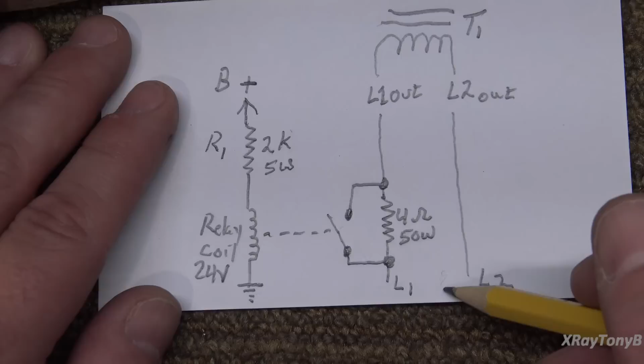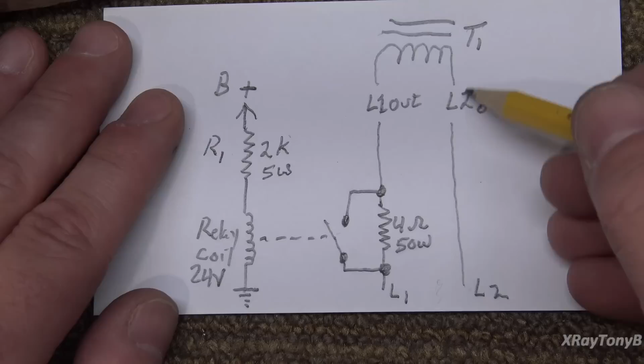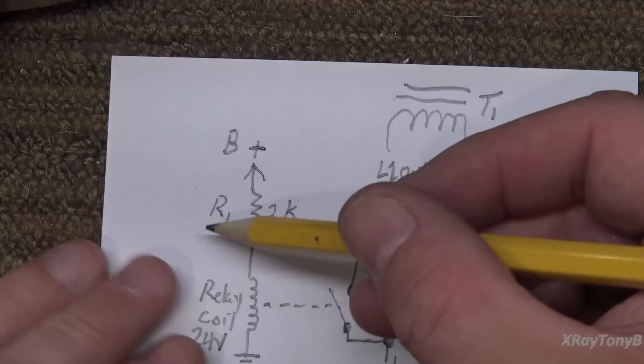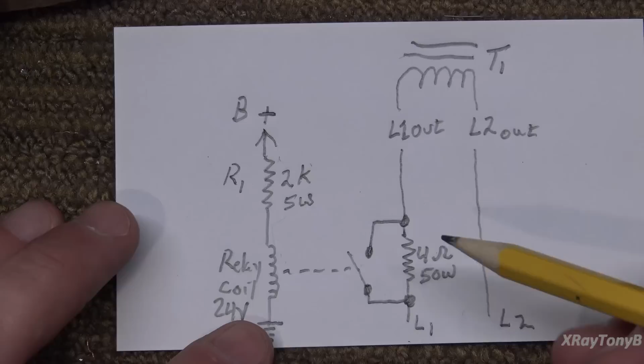Okay, so all that's going to happen is when we plug this thing in, current's going to flow through this resistor, and it's going to limit the current through this transformer, which is going to limit the current getting into the capacitors. Once the capacitors charge up to a certain rate, it'll build up high enough that this voltage drop and this voltage drop will be enough to bring in this relay, and the relay will click in.